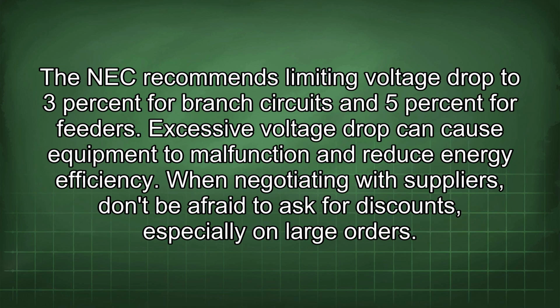The NEC recommends limiting voltage drop to 3% for branch circuits and 5% for feeders. Excessive voltage drop can cause equipment to malfunction and reduce energy efficiency.